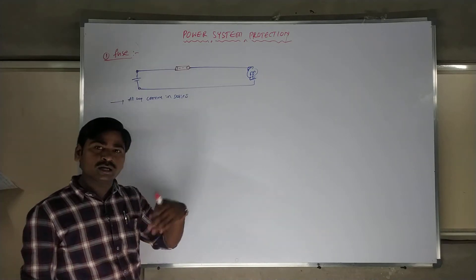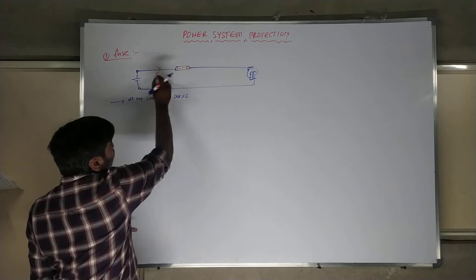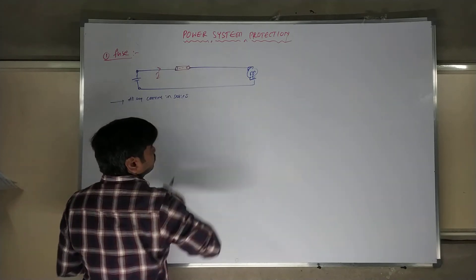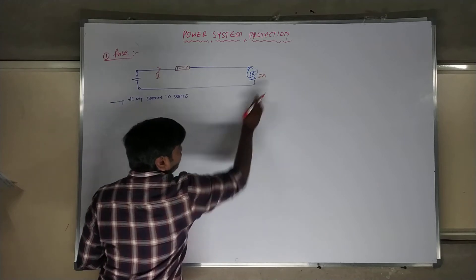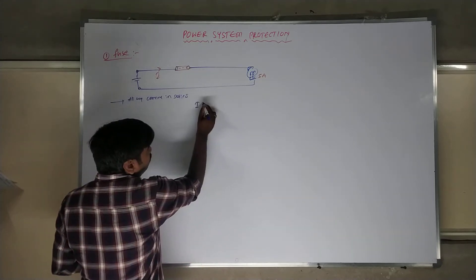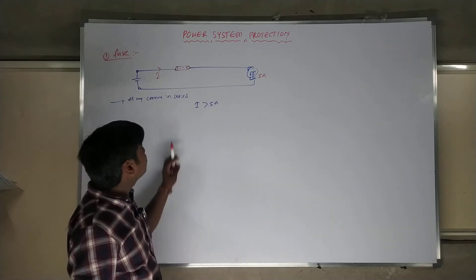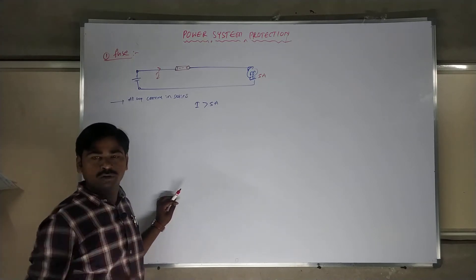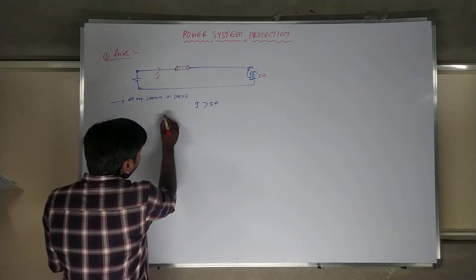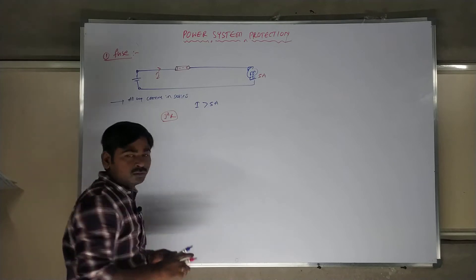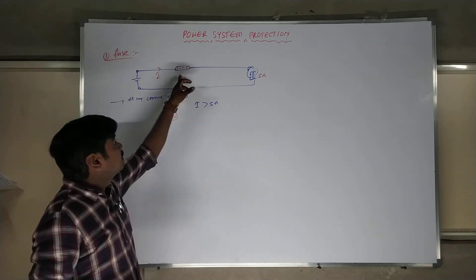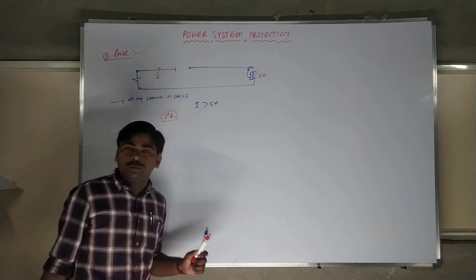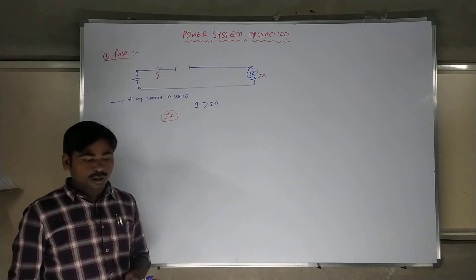Whenever excess current flows through the fuse — more than the rated current — for example, if the motor's rated current is 5 amperes and more than 5 amperes is flowing, the fuse starts heating. Whenever current exceeds the rated value, the fuse starts heating automatically, heat loss takes place (I²R), and at a certain point the wire starts melting. Therefore the circuit will open and your equipment will be in a safe zone. In such a way the fuse protects your system.